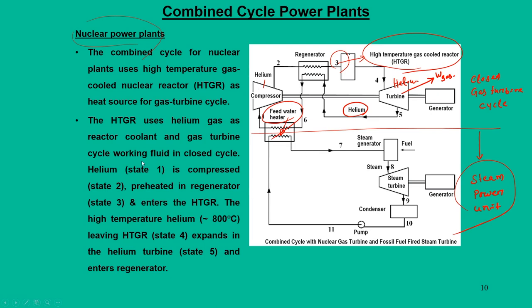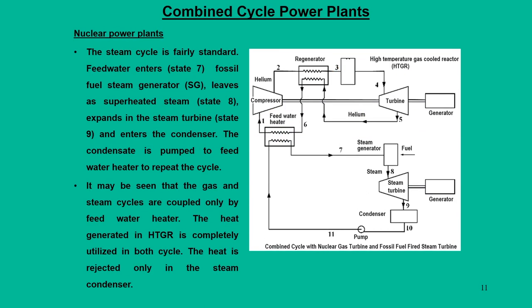Some workable numbers: helium normally operates at very high temperature — 800 degrees centigrade — and can expand to generate power through the gas turbine unit, which is then coupled to the steam cycle through the feed water heater. The heat generated from the HTGR is completely used by both cycles and heat rejected is only in the condenser. This particular arrangement is called a combined cycle with nuclear gas turbine and fossil fuel fired steam turbine unit.